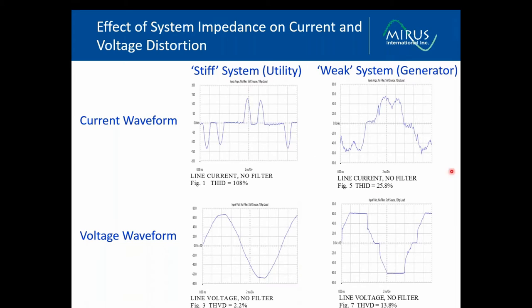This exact same drive, though, when supplied by a weak generator source, draws less current harmonics because the impedance of the source, the generator, limits the amount of harmonic currents that are introduced. But as these currents pass through the impedance of the source, the high impedance of the generator creates voltage distortion. So here we have almost 14% voltage distortion, very sharp flat topping of the voltage, very high distortions. We're talking about the same drive system and the difference between its operation on a weak generator source. And since marine applications are all supplied by generators, we're dealing with these very high levels of voltage distortion.